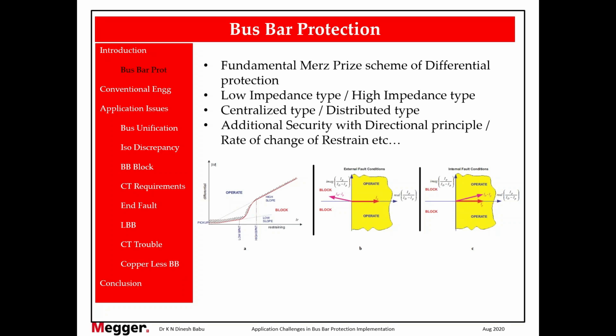So let us take the same example. Out of 10 currents, my differential current is 0, restraint current is, let us say, 1 per unit. Now suddenly one current is invisible because of some secondary issues. What will happen? 9 currents are available. When you calculate, the differential current would have increased, but the restraint current will not increase because, let us take in this example, the maximum current principle. If there is no fault, restraint current will not increase.